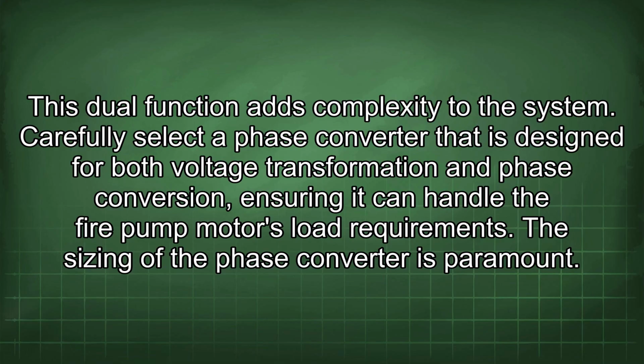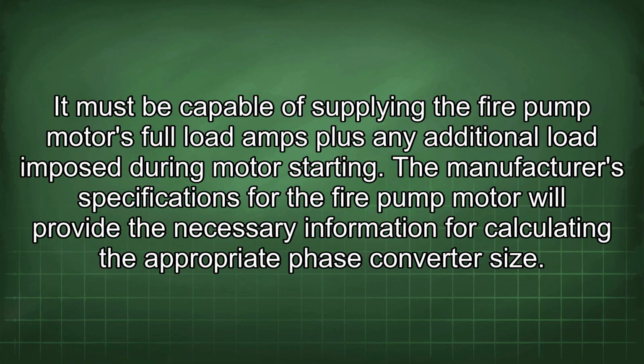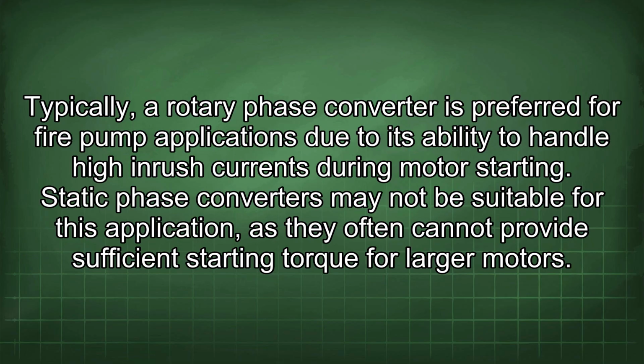The sizing of the phase converter is paramount. It must be capable of supplying the fire pump motor's full load amps plus any additional load imposed during motor starting. The manufacturer's specifications for the fire pump motor will provide the necessary information for calculating the appropriate phase converter size. Typically, a rotary phase converter is preferred for fire pump applications due to its ability to handle high inrush currents during motor starting. Static phase converters may not be suitable for this application, as they often cannot provide sufficient starting torque for larger motors.